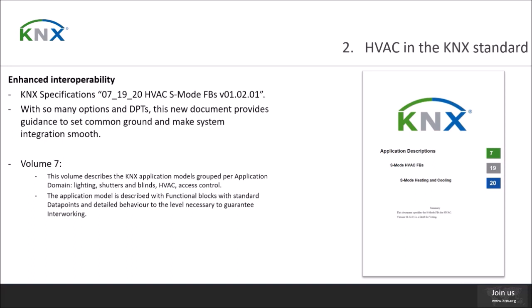Let's imagine a room thermostat from one manufacturer and a fan coil controller from another manufacturer. They could be using existing standardized data points, yet they could not be able to interwork because they use different ones. The purpose of the document 7/19/20 is to make sure that interworking is guaranteed in HVAC devices that are KNX certified.